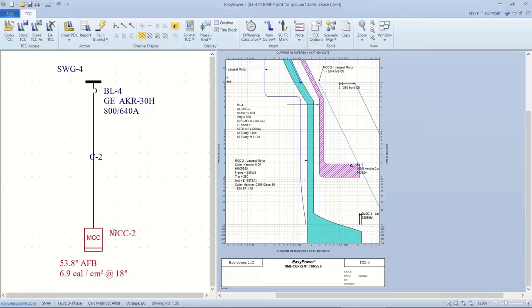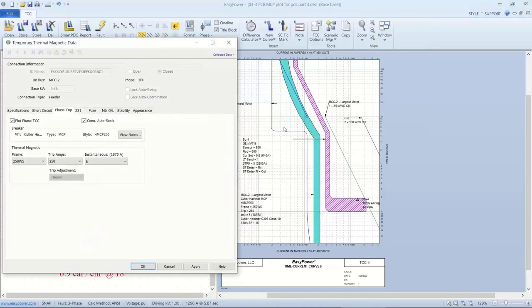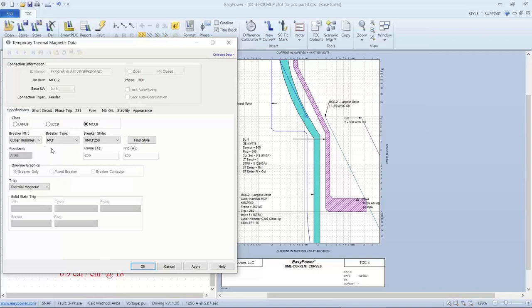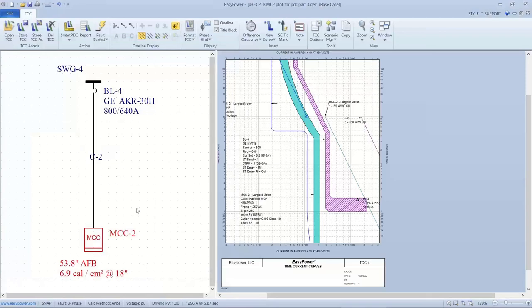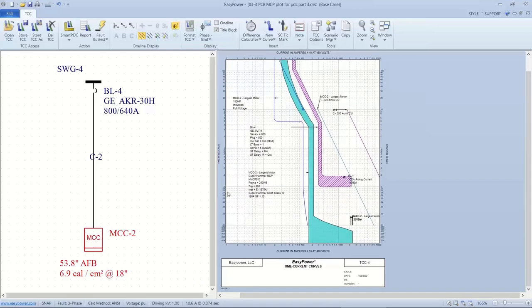The instant energy on this bus is controlled by the BL4 settings. Right-clicking to insert the arcing tick mark, the 100% arcing current where it intersects the magenta breaker's upper plot gives us the clearing time — about 187 milliseconds. The incident energy is about 6.9 calories. Now we have coordination with the LVPCB and the motor circuit protector, though I note I should have the contactor indicated on my one-line as well.